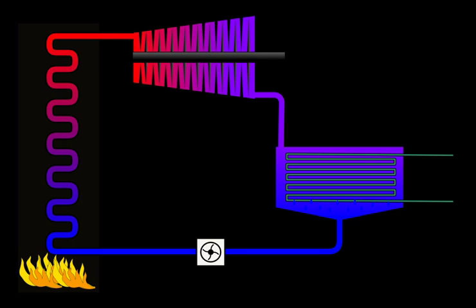The working fluid in a Rankine cycle follows a closed loop and is reused constantly. The water vapor with condensed droplets often seen billowing from power stations is created by the cooling systems. This heat is represented by the Q out flowing out of the lower side of the cycle shown in the TS diagram below. Cooling towers operate as large heat exchangers by absorbing the latent heat of vaporization of the working fluid and simultaneously evaporating cooling water to the atmosphere.